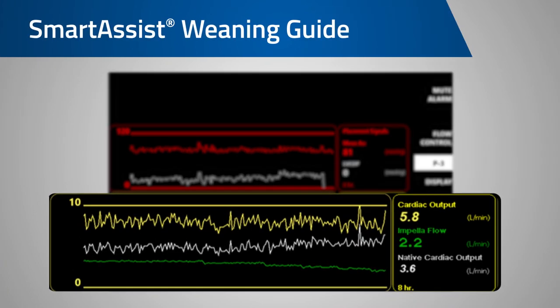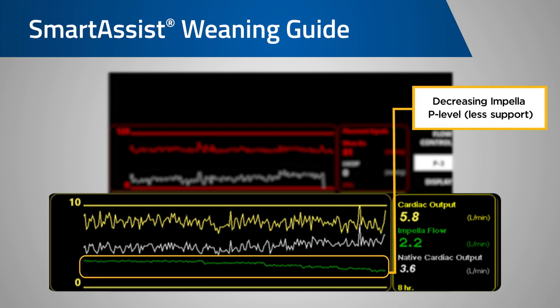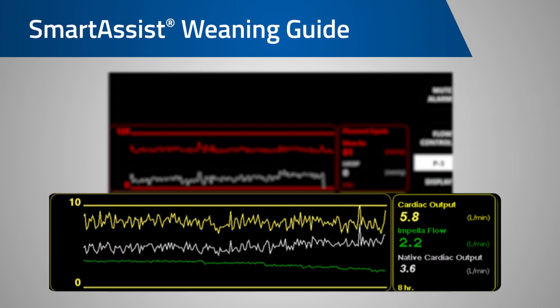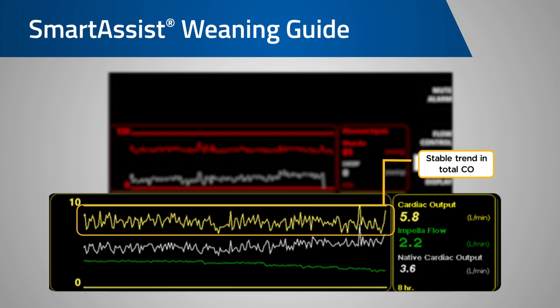Now let's move down to the cardiac output portion of the trend screen. When a reference cardiac output is entered, the automated Impella controller can determine the portion of the cardiac output being provided by Impella and the native heart. As the P levels, shown in green, are decreased, you want to observe an increasing trend in the native cardiac output shown here in white. Additionally, you want to observe that the total cardiac output, shown here in yellow, remains stable.